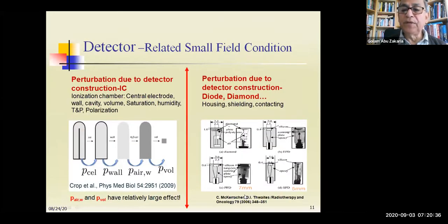Here are detector related small field conditions. You know there are many perturbation factors in detectors which can be corrected in the protocol so that we have a precise dose. On the right side, I have given some photos. In every photo, the left side is a schematic diagram, and the right side is a photo taken with X-ray. Before you use different types of detector, you should first take photos with X-ray, because you want to know whether inside the detectors there is a mistake or some defect. And this is very important for small field dosimetry.